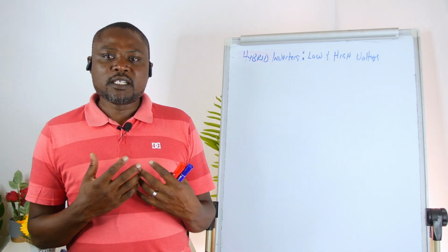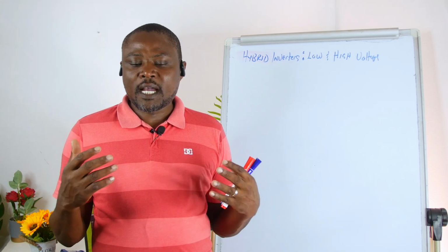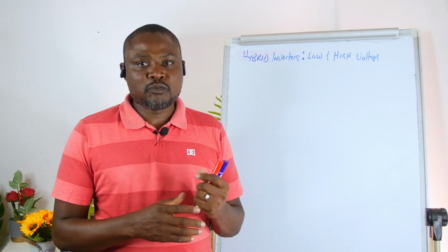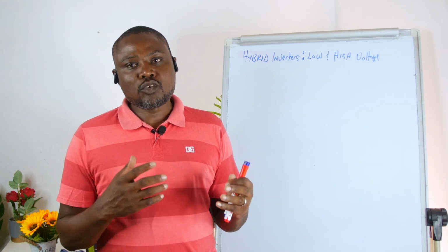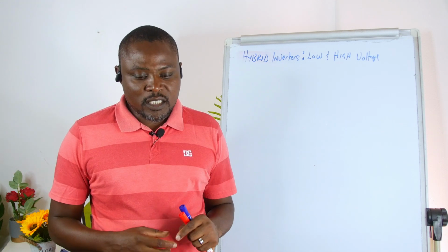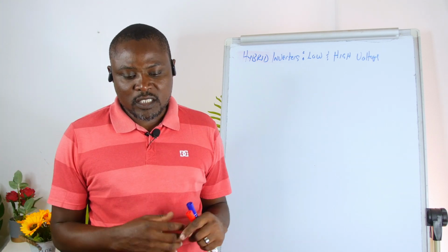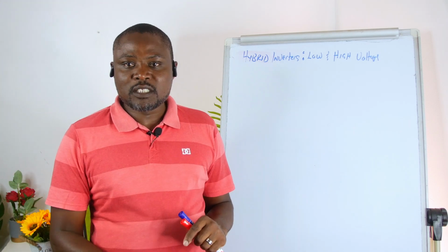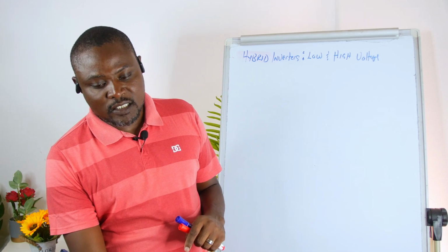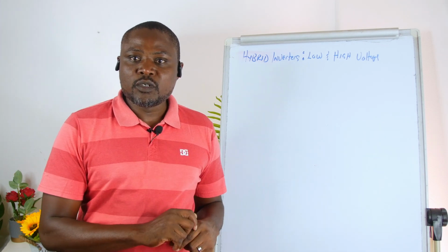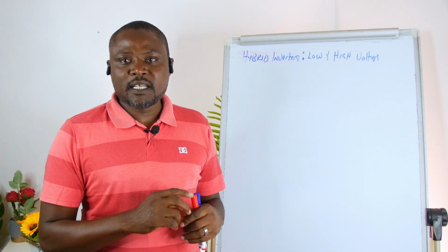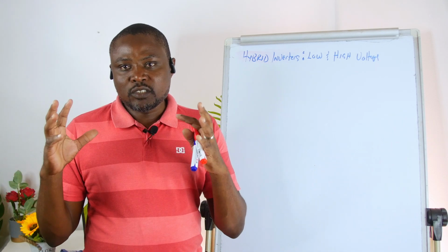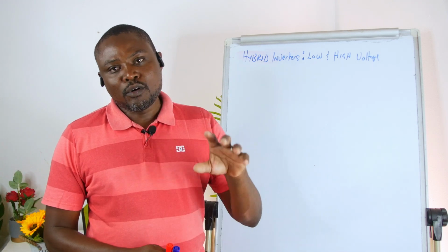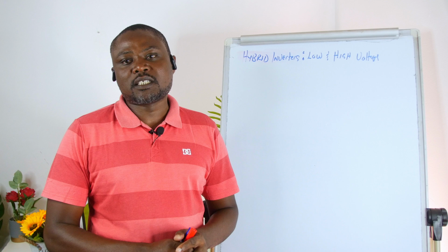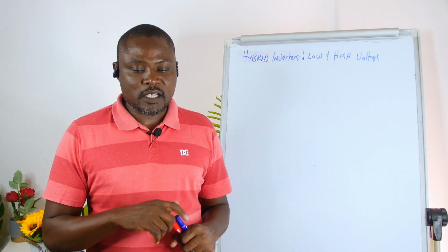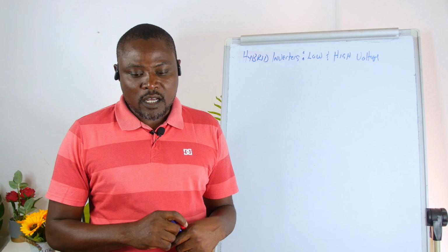The advantage of hybrid is affordability, low cost of buying a single unit, easy to install because all components are in one unit, and also they give a good finish once the setup is completed. But at the same time, the downside is when there's a breakdown with this particular system, the entire unit is down and you need to get it replaced, vis-a-vis the traditional setup where you have your inverter and your MPPT separately. If your MPPT breaks down, you can quickly take it out of the equation and still continue to have your inverter powering your loads whilst you get that resolved.